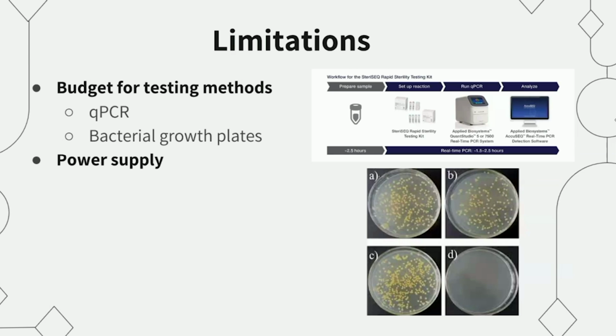However, we've also encountered limitations to our project. For example, the gold standard in sterility verification, which we would like to run before and after using our device, is qPCR. However, qPCR testing is prohibitively expensive both for us and in a low-resource setting. Our alternative for prototyping is to swab the instruments before and after cleaning onto agar plates and monitor the bacterial growth over time. Another limitation we've encountered is the power supply for our device. We have tested from 5 to 18 volts of power, but have had issues with transducer operation. To fix this, we're looking into higher voltages and using 100-watt drivers.